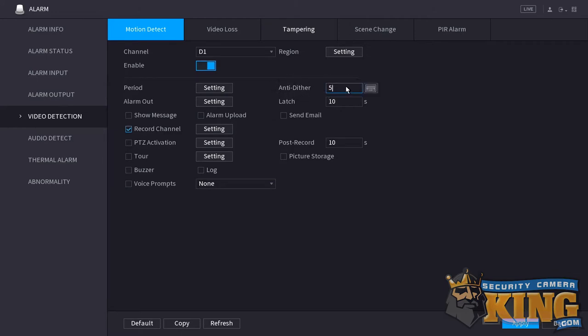Another setting relative to both of these is anti-dither. Anti-dither is just a timer between 0 and 100 seconds that starts once both the sensitivity and threshold criteria have been met. If you have anti-dither set to 5 seconds, which is the default, then 5 seconds will have to pass before an event is logged as motion. All three of these settings work together to help you eliminate false alarms.